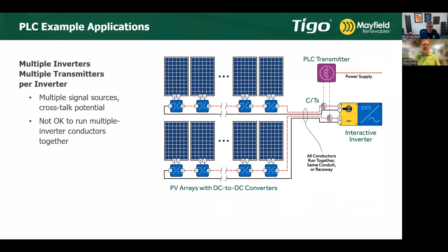Let's talk about multiple inverters with multiple transmitters per inverter, getting into much larger systems. With the first inverter, all the conductors on that single transmitter are no problem, we can run those together. We'll truncate this array a bit and add another inverter with the same kind of setup, keeping everything separated.